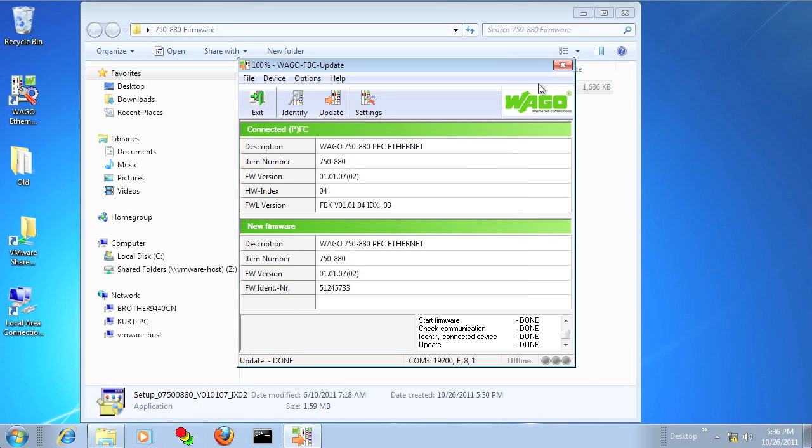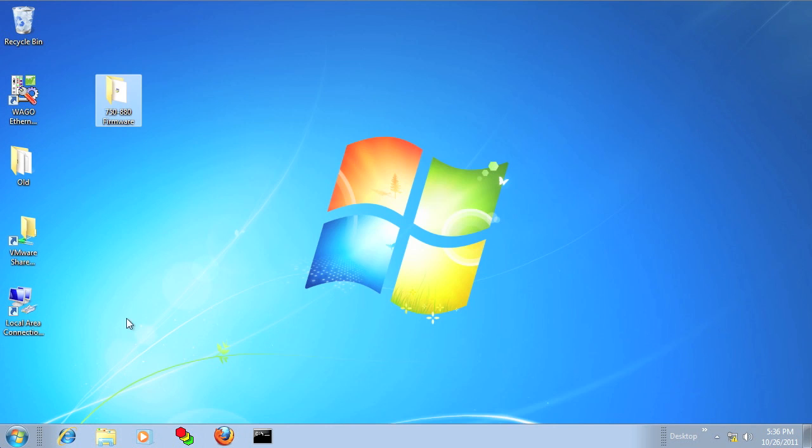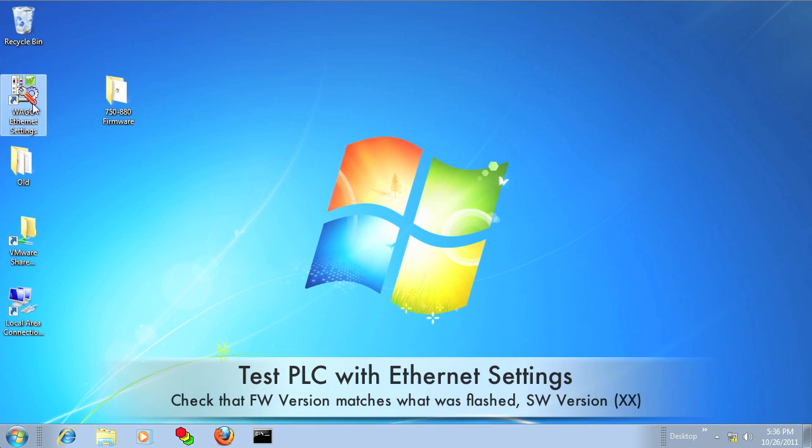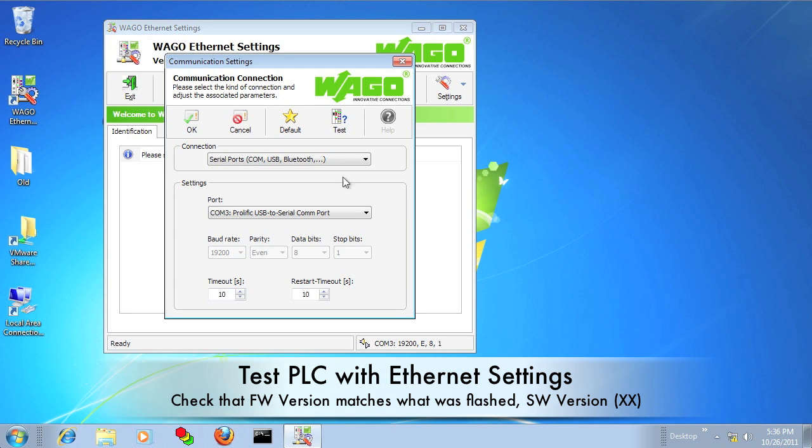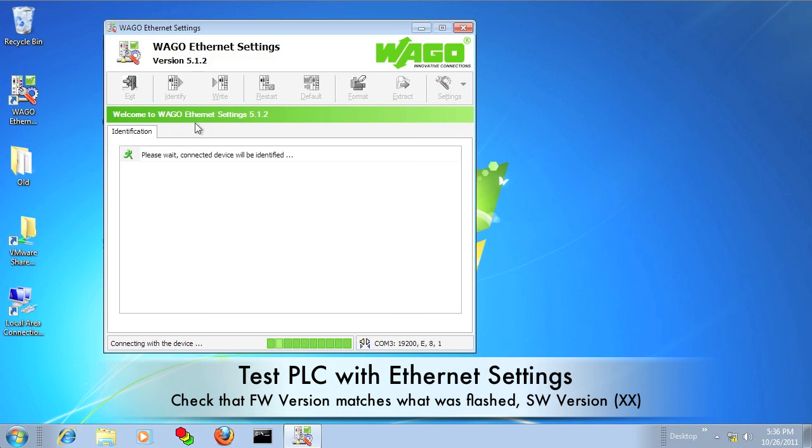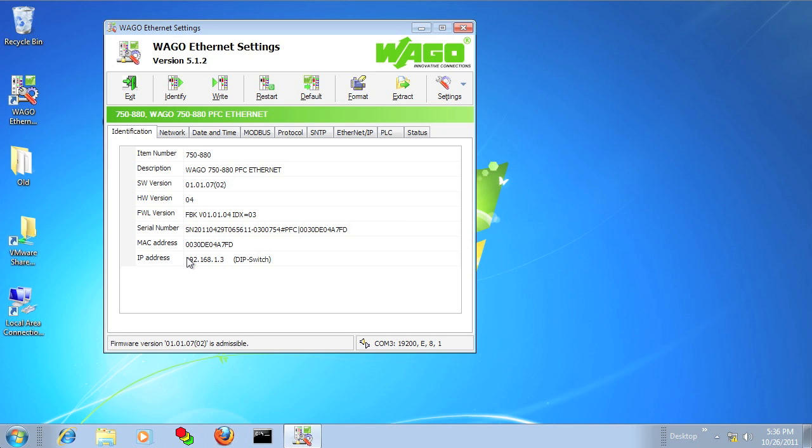This next step is optional. I like to go into WAGO Ethernet Settings and verify that the firmware indeed transferred correctly. You can locate the firmware version that's on the controller by going to the Identification tab and looking at Software Version, and the number in the parentheses is the firmware version.